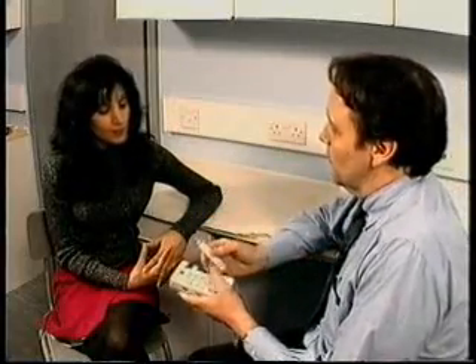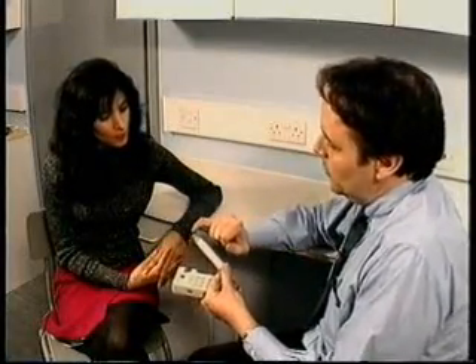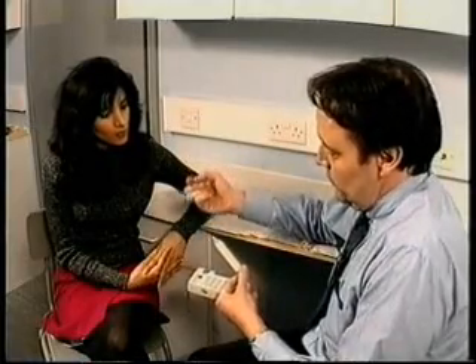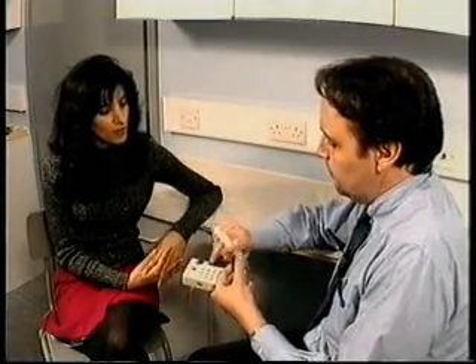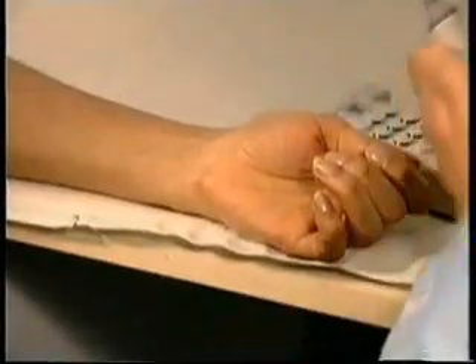So Jeff, how does it work? Well, this is a very simple Doppler ultrasound instrument, and we have a probe here which transmits a beam of ultrasound and which receives the echoes from structures which are in that beam. Because the speed of sound in tissue is about 1,500 metres a second, and the maximum speed of blood in the body is about 1 metre a second, if we use ultrasound in the region of a few megahertz in frequency, the Doppler shift is of the order of a few kilohertz, which is audible. And that means that we can hear the Doppler signal, despite the fact that we're using ultrasound actually going into the patient.